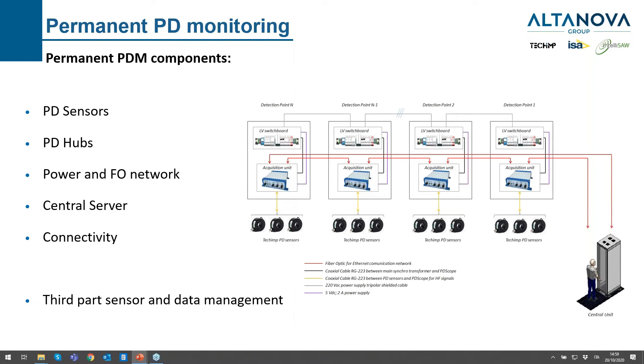The components of permanent monitoring are: the sensor, where the analog signal is picked up from the asset; the PD acquisition unit, which takes the analog signal and digitizes it; the power and fiber optic network — power energizes the monitoring, and fiber optic takes the digital signal from the acquisition unit to the central server. In the central server, all data elaboration occurs, with connectivity to internet, local SCADA, and so on.